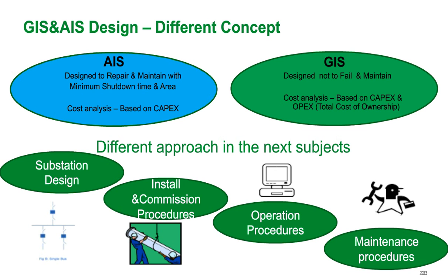There is an analysis that has to be done to compare the number of breakers for the whole footprint of the lineup. So I'll never say with 100% assurance that a GIS lineup at 15 kV is going to be more compact than metal-clad at 15 kV, because there's sort of a break-even point. But in a lot of cases, if it's a simple lineup and you take into account the reduced risk of fault and arc resistance, that can move you to choose GIS over AIS.